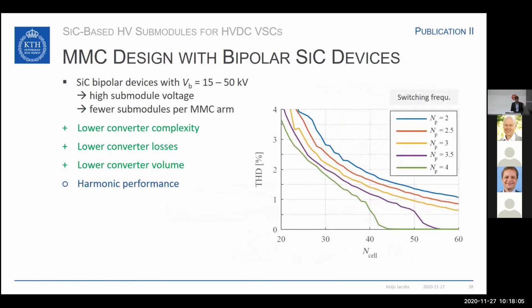Another issue that has to be considered with such a converter design is the harmonic performance. In this case, I show the total harmonic distortion on the y-axis and the amount of submodules on the x-axis. Each of these curves represents the total harmonic distortion for a certain switching frequency. N_p here is the pulse number. So a pulse number of 2 would correspond to a switching frequency of 2 times the fundamental. In this case, 2 times 50 hertz is 100 hertz.